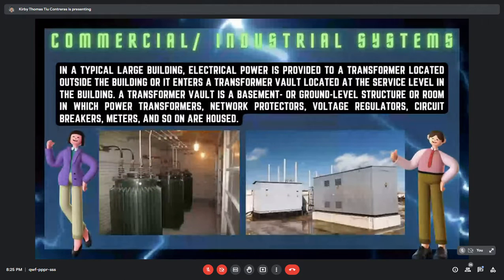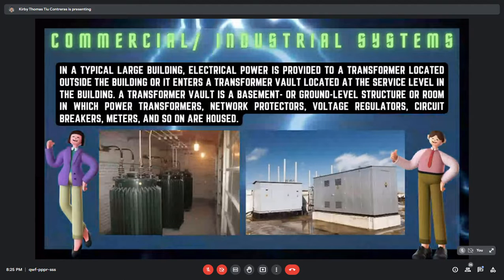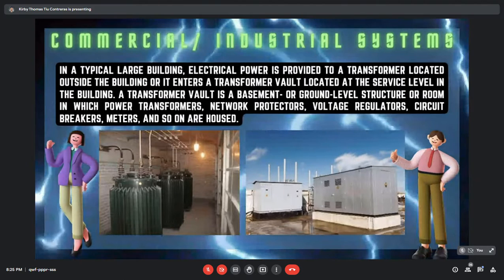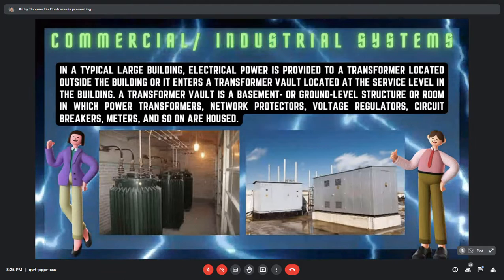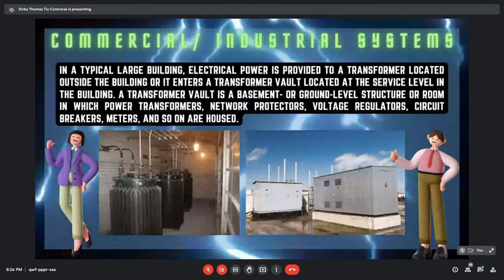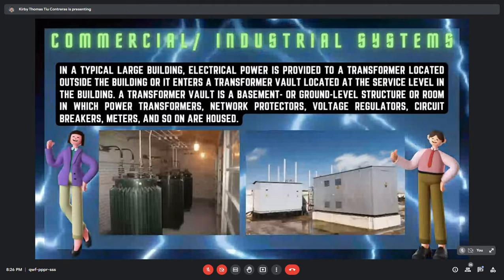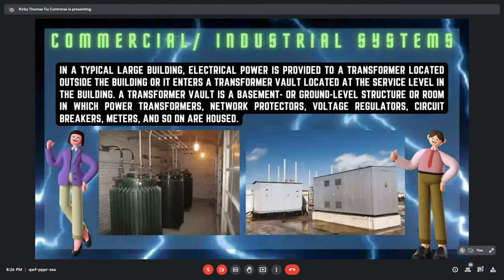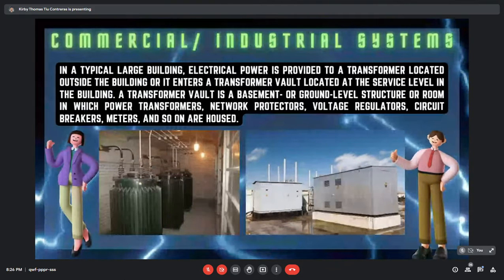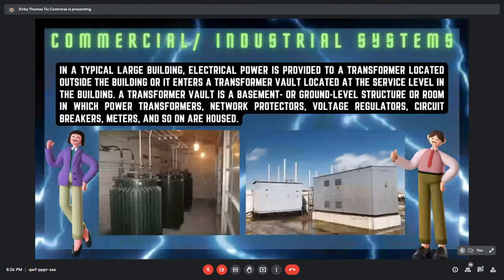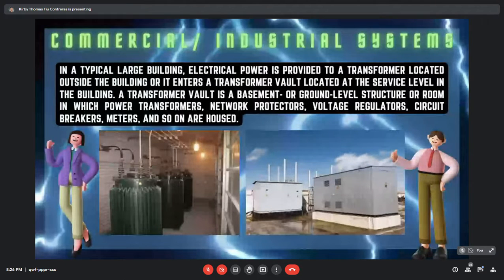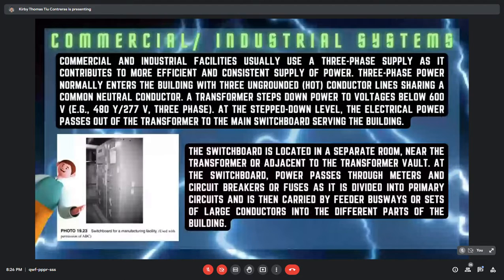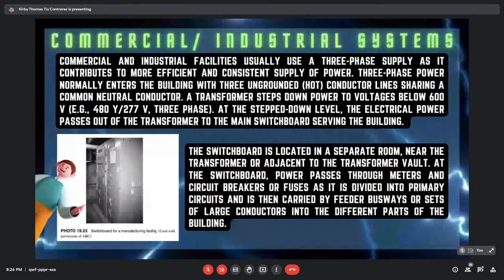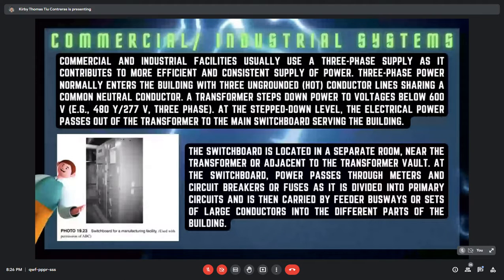So, in a typical large building, electrical power is provided to a transformer located outside the building, or it enters a transformer vault located at the service level in the building. A transformer vault is a basement or ground level structure or room in which power transformers, network protectors, voltage regulators, circuit breakers, meters, and so on are housed. Commercial and industrial facilities usually contribute to a more efficient and consistent supply of power.